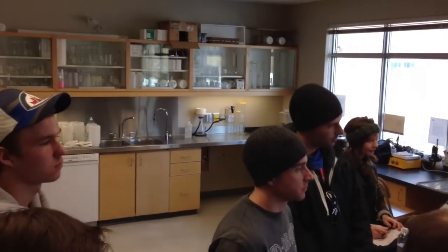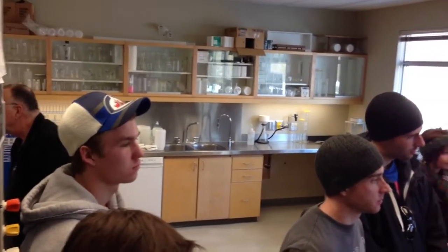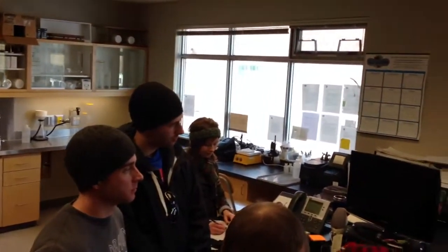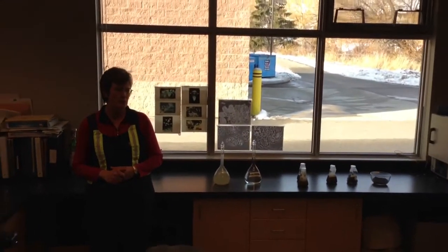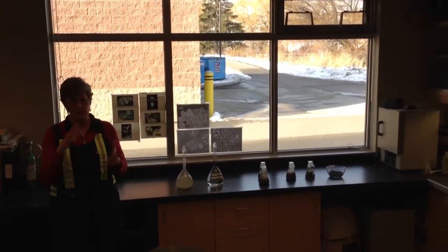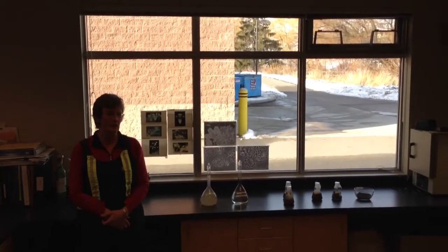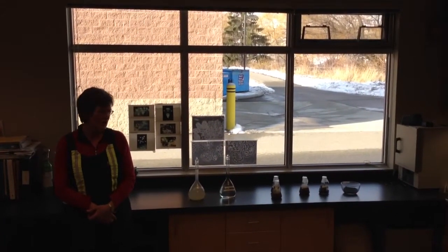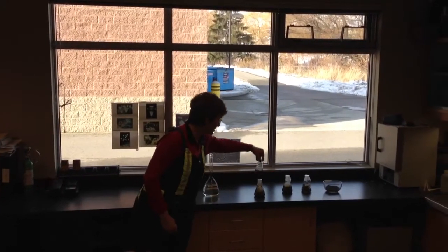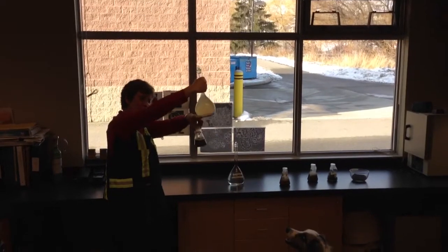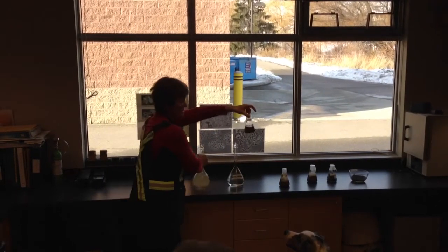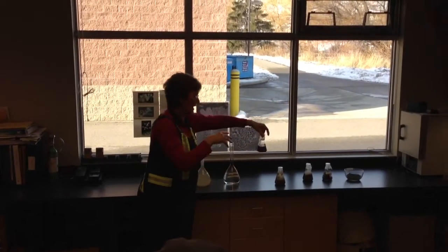Then we have a primary clarifier, and that will just settle the quickly settling solids. That's mostly inorganics, that's sand and grit. That will go to our fermenter. The fermenter then is an anaerobic treatment tank. It just is a longer term. There are bacteria in there that don't require oxygen, and they remove these kind of solids. This is what goes to the fermenter.